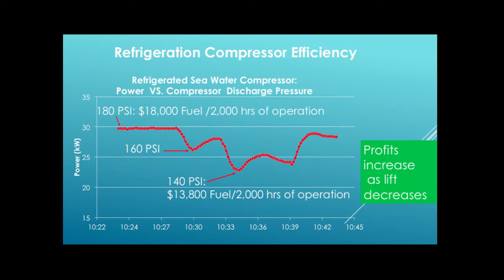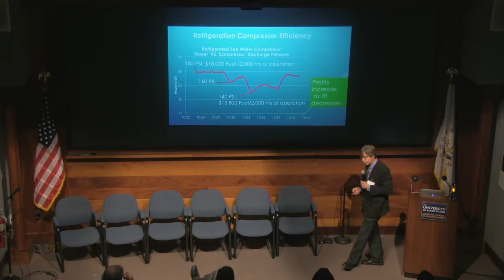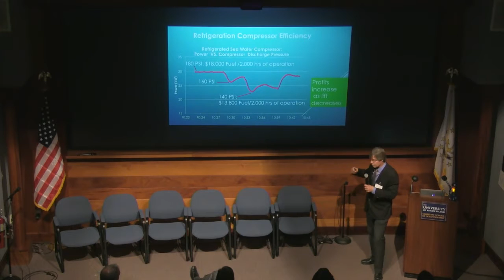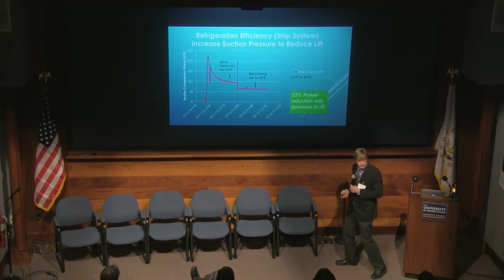So now we've increased the capacity of the machine, we lowered the head down, saved them some money, but when we end up with extra capacity when you're in the low requirement mode, when everything's already pulled down, well then you end up with the unit cycling. So now we have capacity control that we have to deal with. I think I'm running slow here, so I have to go quick.